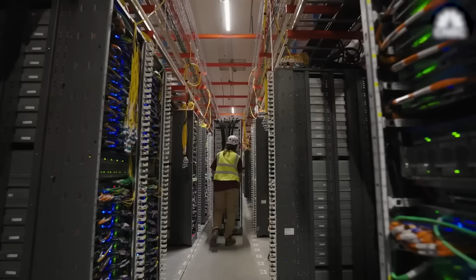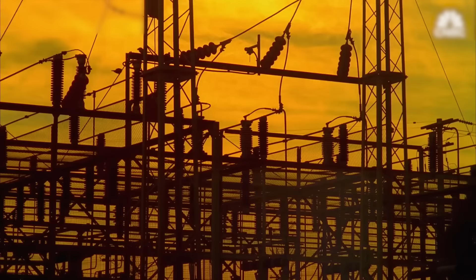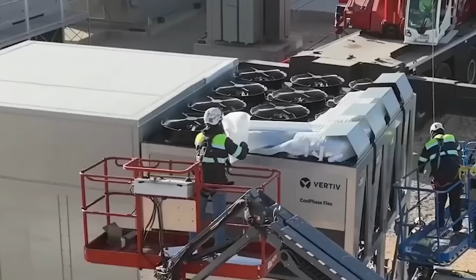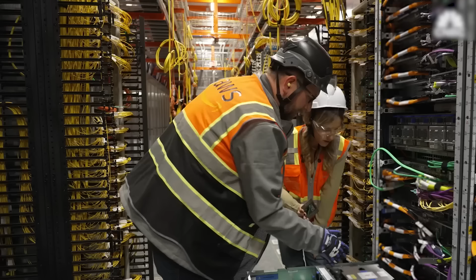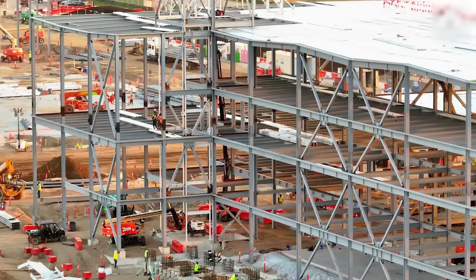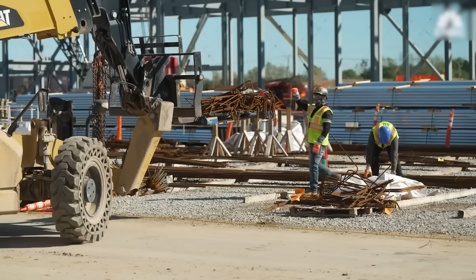Commissioning activity becomes a major focus during this period. Newly completed data halls undergo stage testing, including power load validation, cooling performance verification, and failover simulations. These processes occur while adjacent buildings remain under construction, requiring strict operational separation and safety controls.